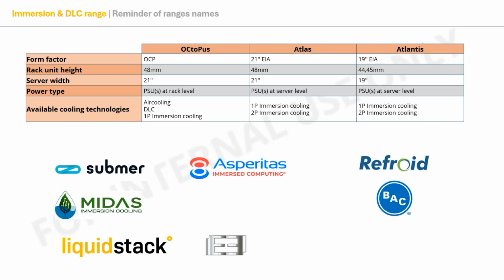In Octopus, we have air cooling, DLC, and 1-phase immersion cooling. We don't do dual-phase immersion cooling in Octopus at this moment, because we don't know of any tank that can provide OCP for dual-phase right now. But in Atlas, we can do two-phase immersion cooling as well as one-phase immersion cooling. So Atlas and Atlantis are the ranges in the two-series side that only do immersion cooling at this moment.